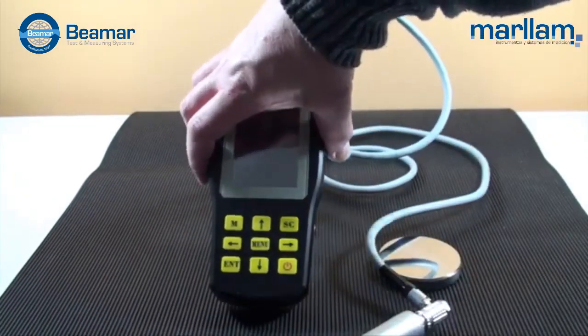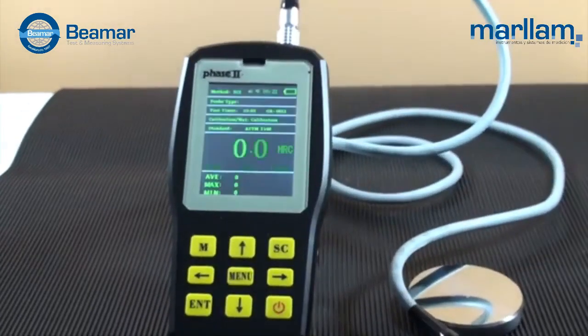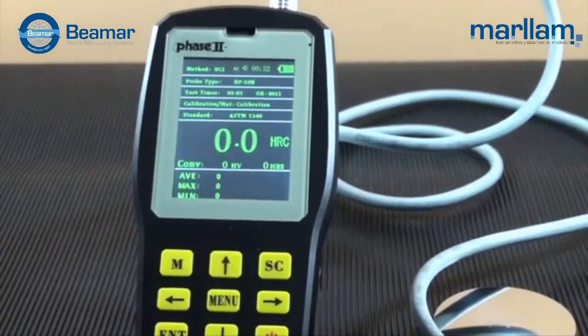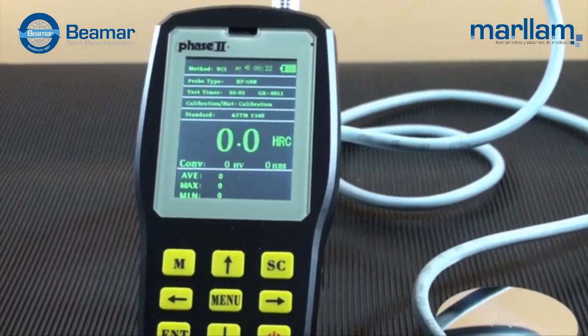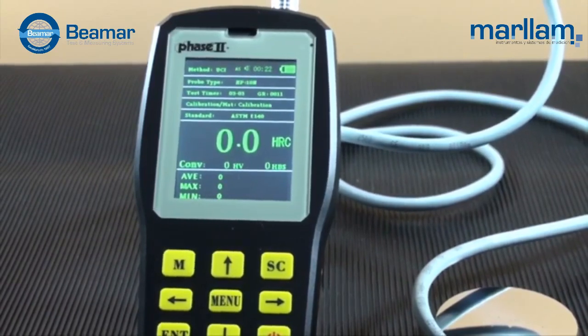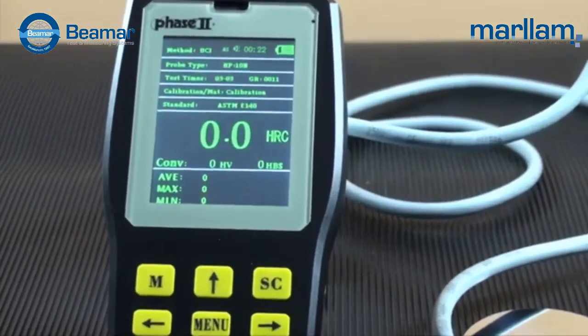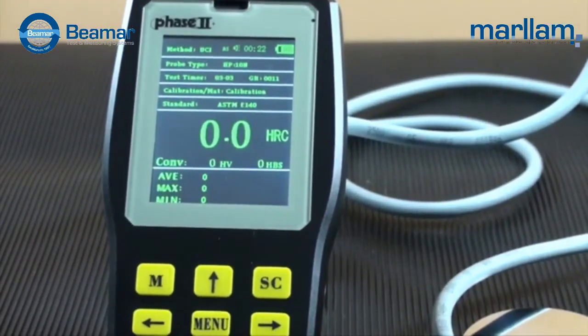Power the unit on from the left side of the body. The interface will show you at top left the method of test being used, either UCI or Leeb. A timestamp is at the top, and to the far right is the battery indicator level. Just below is the probe type, then test times for average, then group number, your calibration scale setting, and material. The international standard being used for reference, the actual hardness reading with scale on the right. Just below is the conversion showing if selected. And below that are basic statistics, average, maximum, and minimum. The interface will power off after a short time without using the tester.